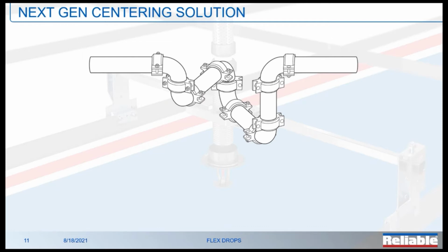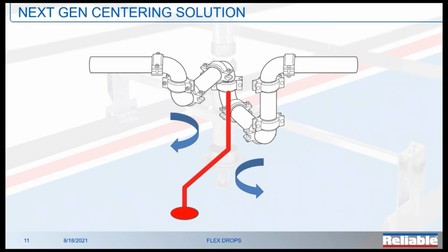It was done with threaded couplings. But imagine at that point if we swung down, broke back under ourselves, and then went down to our drop. So now you've got this 90 bend that at the top and the bottom, you could move in 2 different directions. And within a particular range, a radius, you could hit center of tile, provided, again, that the ceiling didn't change too much.